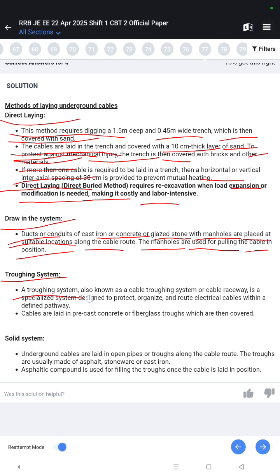Draw-in system: ducts or conduits of cast iron, concrete or glazed stone are used, with manholes placed at suitable locations along the cable route. The manholes are used for pulling the cable into position. Troughing system. A troughing system, also known as a cable troughing system or cable raceway, is a specialized system designed to protect, organize, and route electrical cables within a defined pathway. Cables are laid in precast concrete or fiberglass troughs which are then covered.